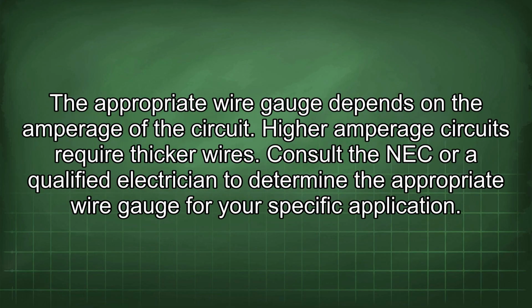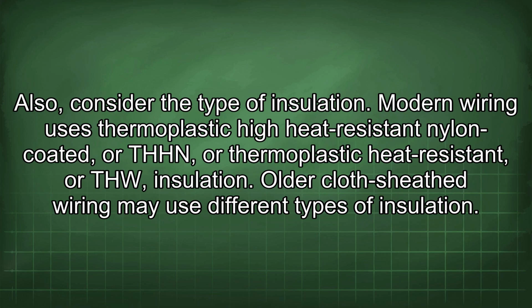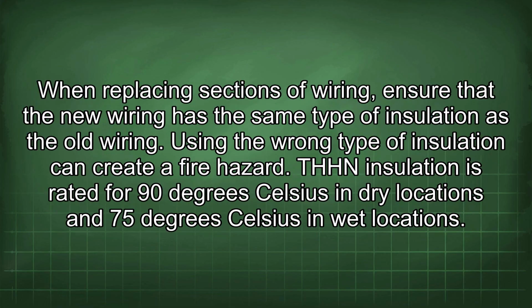The appropriate wire gauge depends on the amperage of the circuit. Higher amperage circuits require thicker wires. Consult the NEC or a qualified electrician to determine the appropriate wire gauge for your specific application. Also, consider the type of insulation. Modern wiring uses thermoplastic high heat resistant nylon coated, or THHN, or thermoplastic heat resistant, or THW, insulation. Older cloth-sheathed wiring may use different types of insulation. When replacing sections of wiring, ensure that the new wiring has the same type of insulation as the old wiring. Using the wrong type of insulation can create a fire hazard.